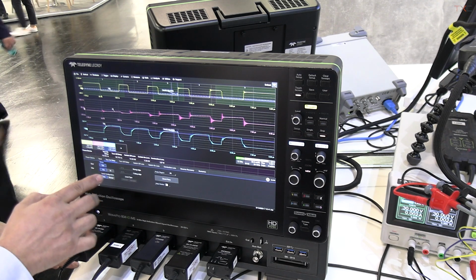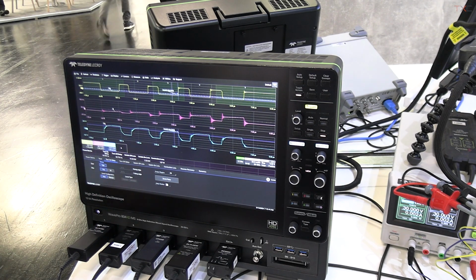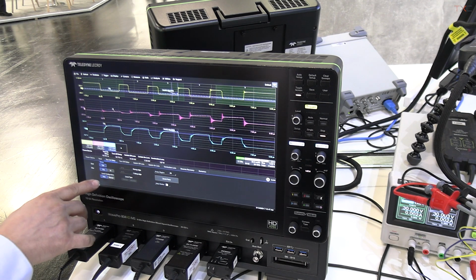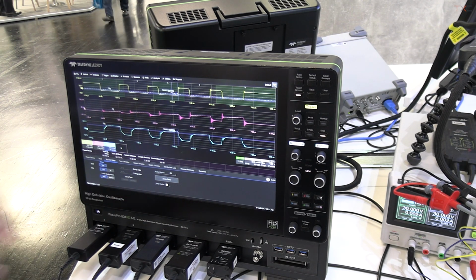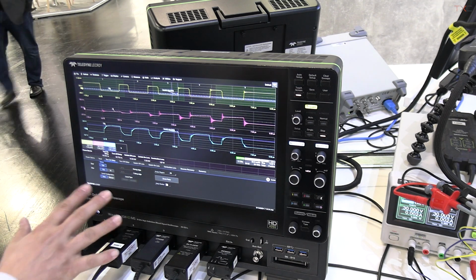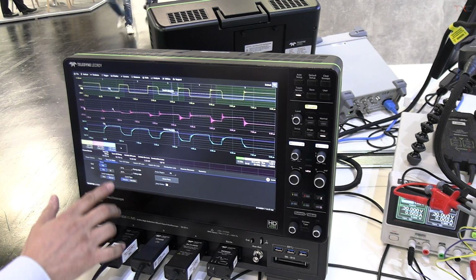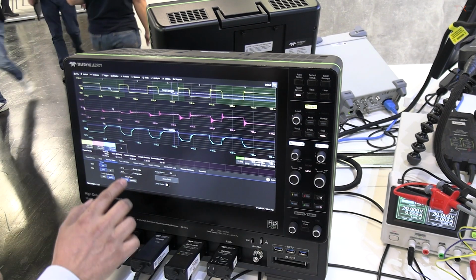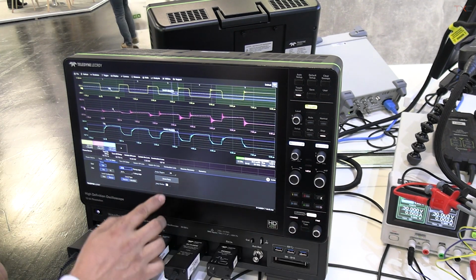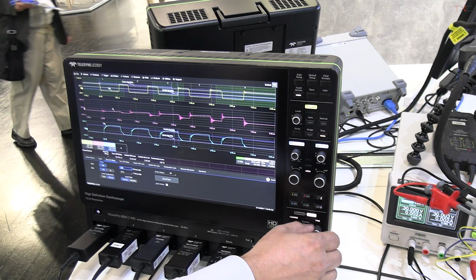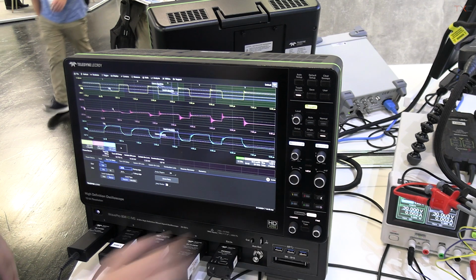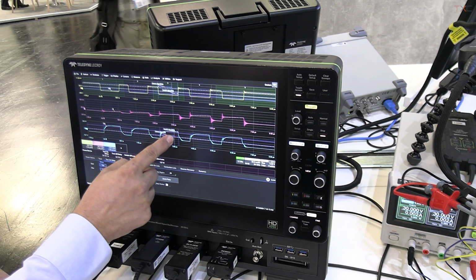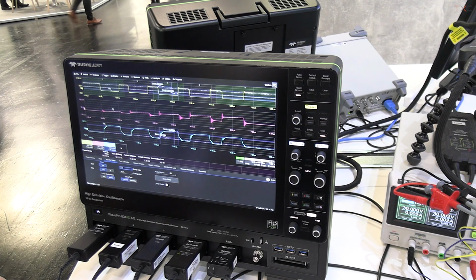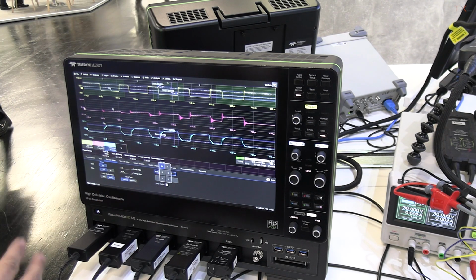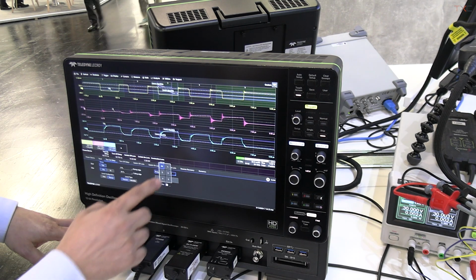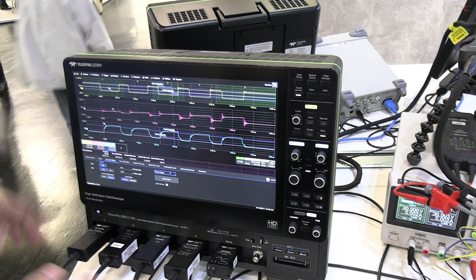Then we can go into these measurements. As I said before, we follow the proposal from the JEDEC. If you go to auto measurement, the values where to measure the delays are set to the JEDEC proposal. Otherwise, you go to manual, and then you can select individual values where to make your measurements. If you switch on the help markers, you also see the voltage levels where you measure on the signal, and you can even click here and move these values around to the desired position on the screen. Then you can decide on what region you measure, either all of them or just a specific area where you want to do the measurement.